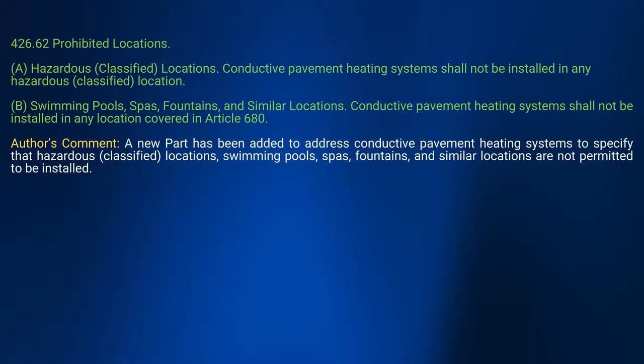Now there's a lot that's going to take place here. They added a whole new part, redoing this, dealing with conductive pavement heating systems. They tell you there's prohibited locations for this type of heating system—you can't install it in hazardous classified locations, and you can't install it where there's swimming pools, spas, fountains, and similar locations.